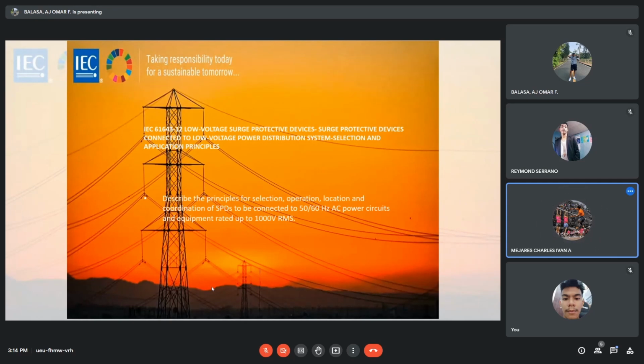IEC 61643-12, low voltage surge protective devices, surge protective devices connected to low voltage power distribution systems, selection and application principles. Describes the principles for selection, operation, location, and coordination of SPDs to be connected to 50 or 60 Hz AC power circuits and equipment rated up to 1000 volts RMS. This device also contains at least one nonlinear component and is intended to limit surge voltages and divert surge currents. Next.